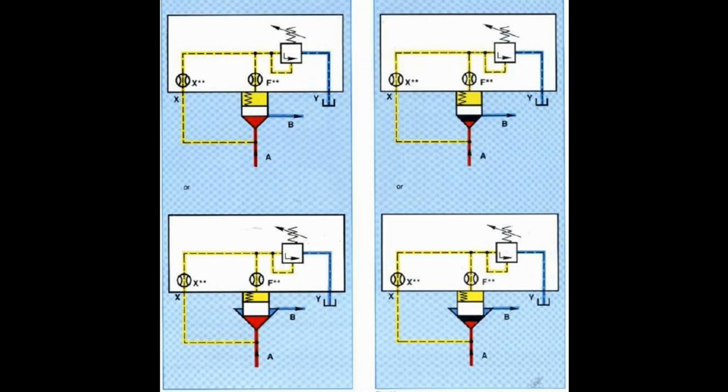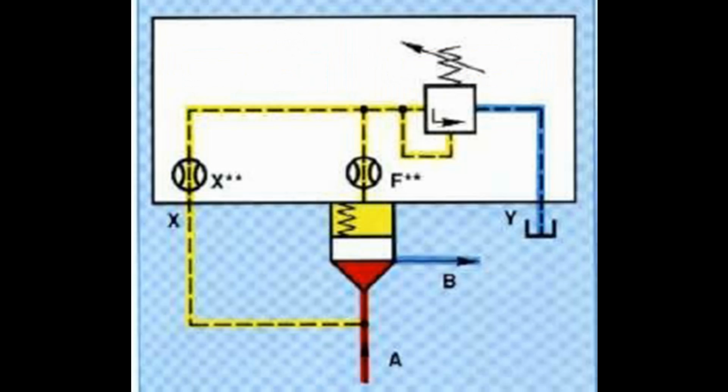When the system pressure reaches the level set at the pilot valve, 3, fluid flows via the orifices in the control line to tank via Y. Pressure setting is via the pilot valve, 3. The pilot valve itself is a direct operated pressure relief valve. A pressure drop occurs across orifice 7, which causes a difference in pressure between the ends of the main spool.